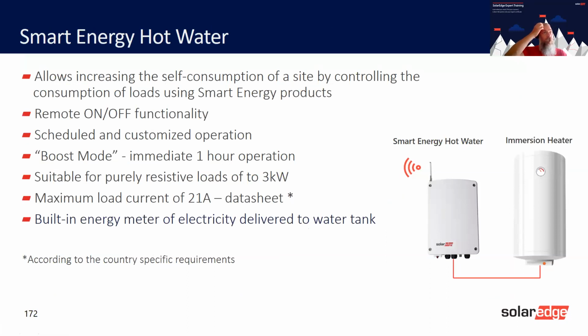It has a boost mode as well, so you can set it to heat up for 1 hour just by moving the switch. You can get it to heat up for an hour, or it will work off excess PV or a schedule. It also has an energy meter, as I said, and you'll be able to record the value you're using. And this is resistive, so this will be from 50 watts up to 3 kilowatts, where the others will be 0 to 3 kilowatts. These will be any value in between.